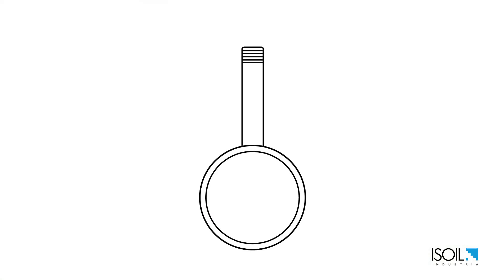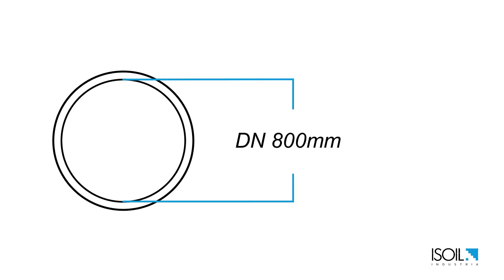Then we need to define the insertion length. Let's assume the pipe has an internal diameter of 800 millimeters. So 800 divided by 8 gives an insertion length of 100 millimeters.